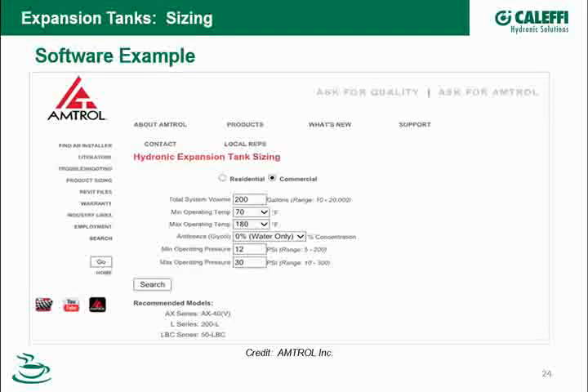Yeah, the minimum operating temperature could be a wide variety of numbers, and it really comes down to this: the lower I push that temperature for the sizing, the larger the tank is going to become. A lot of times I've seen, and this goes back a few years when I was doing expansion tank sizing, a lot of times I would see guys revert to 70 degrees, which is why I went to 70. They reverted to that temperature rather than going to something lower, because when you filled the system, purged it, heated it up, and got rid of all the air, after that first cycling of the system, depending on whether the mechanical room is heated or not, a lot of times a hydronic heating system never drops back down below that 70-degree number. So I did used to see a lot of guys use that. That's kind of why I went with that number on the screen itself.